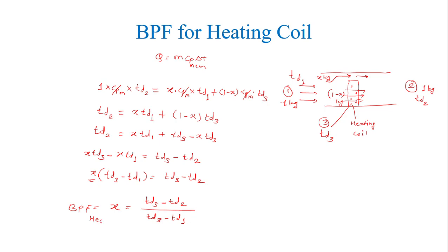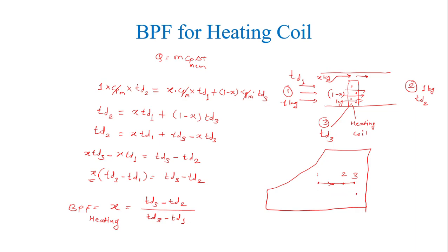This is the bypass factor for the heating coil. On the psychrometric chart, this is a sensible heating process. Point one is the inlet, ideally heating should reach point three (the coil surface temperature), but due to losses, heating only reaches point two. So the bypass factor is the unaffected difference (td3 − td2) divided by the maximum possible heat transfer (td3 − td1) — essentially the loss divided by the maximum possible heat transfer.